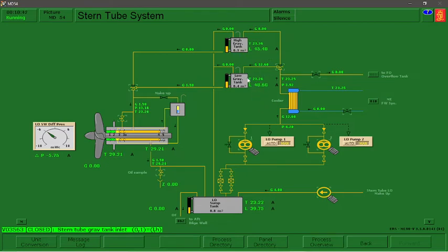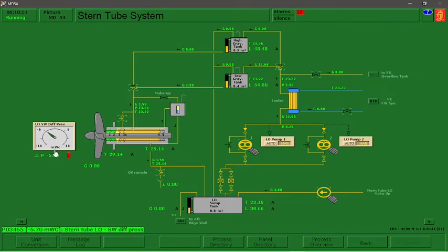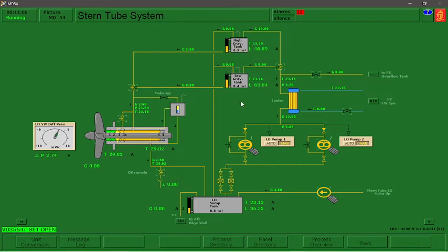When we were using the low gravity tank, we received a low level alarm and a negative differential pressure in our lube oil system. We need to avoid that. By using the high gravity tank, we can achieve the normal differential pressure reading.